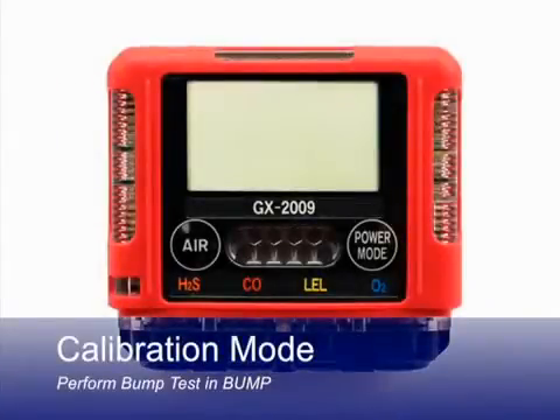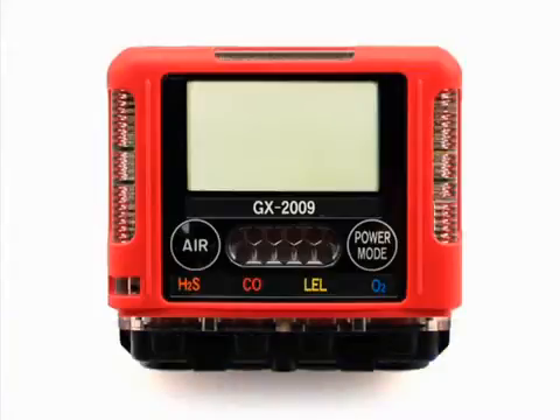The bump menu item will appear in calibration mode only if bump test function is turned on using the GX 2009 user setup program. If bump test function is off, the bump menu item will not appear in calibration mode and you will not be able to perform a bump test. Before performing a span adjustment, perform a fresh air adjustment.